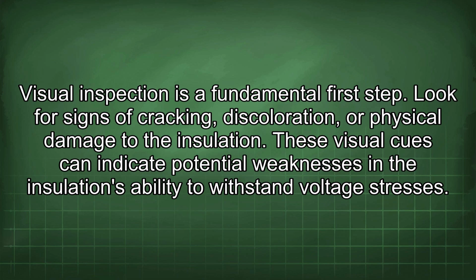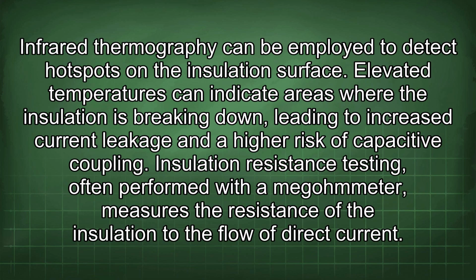Visual inspection is a fundamental first step. Look for signs of cracking, discoloration, or physical damage to the insulation. These visual cues can indicate potential weaknesses in the insulation's ability to withstand voltage stresses. Infrared thermography can be employed to detect hotspots on the insulation surface.